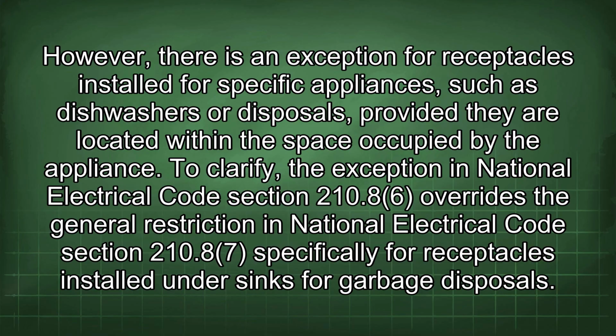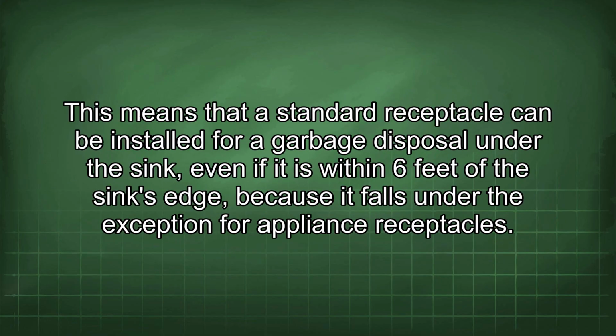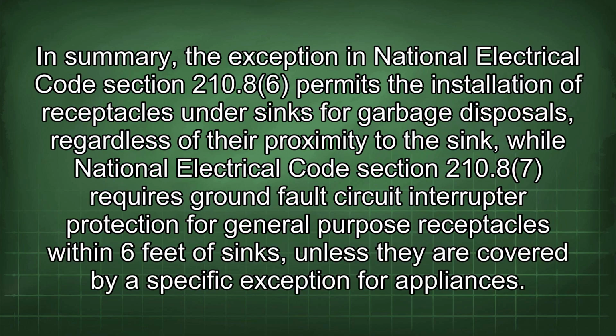To clarify, the exception in National Electrical Code Section 210.86 overrides the general restriction in Section 210.87 specifically for receptacles installed under sinks for garbage disposals. This means that a standard receptacle can be installed for a garbage disposal under the sink even if it is within 6 feet of the sink's edge, because it falls under the exception for appliance receptacles. In summary, the exception in Section 210.86 permits the installation of receptacles under sinks for garbage disposals, regardless of their proximity to the sink, while Section 210.87 requires ground fault circuit interrupter protection for general-purpose receptacles within 6 feet of sinks, unless they are covered by a specific exception for appliances.